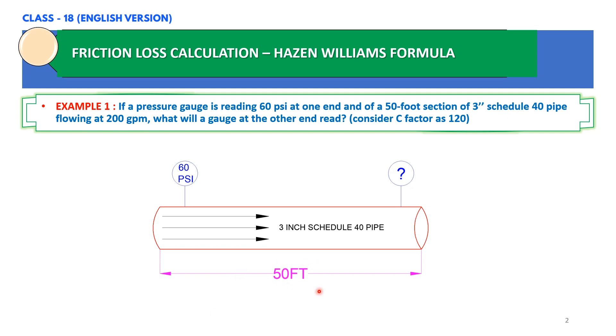As you can see on your screen, we have a straight pipe of 50 feet length, the pipe size is 3 inch, and the material is carbon steel schedule 40. At the starting point of the pipe we can see a 60 PSI pressure reading. We need to calculate the friction losses along the pipe and also the pressure gauge reading at the end of the pipe. The flow rate given is 200 gallons per minute and the C factor for carbon steel pipe is given as 120.